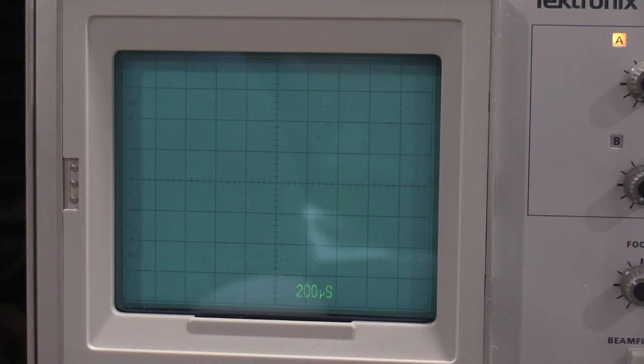So, let me pull the schematic and take a look at where the probe readouts are generated, and where the readout is generated in channel 2, and then we'll go from there just to prove that it's the plug-in and not the scope. I hope it's the plug-in and not the scope. Yeah, it's the plug-in and not the scope.